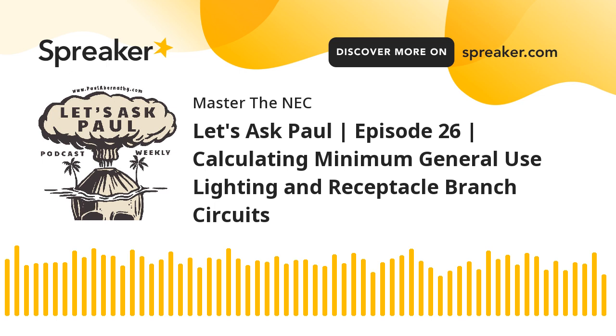Okay, so in a future episode, we will talk about the issues of ampacity ratings of receptacles, and what breaker sizes you can use when you have a single receptacle on an individual branch circuit. For example, you can't take a 20 amp receptacle and put it on a 15 amp overcurrent device, but you can have a 15 amp overcurrent device and put it on a 20 amp receptacle. It's perfectly fine. So there are different things that you can do.